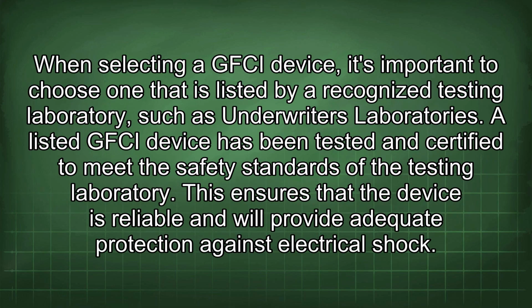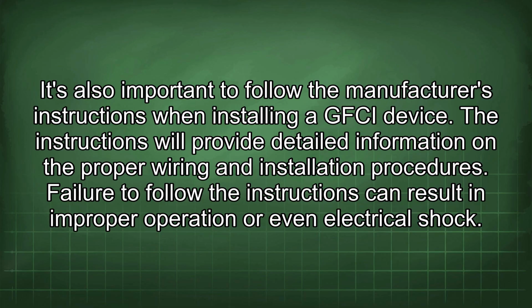When selecting a GFCI device, it's important to choose one that is listed by a recognized testing laboratory, such as Underwriters Laboratories. A listed GFCI device has been tested and certified to meet the safety standards of the testing laboratory. This ensures that the device is reliable and will provide adequate protection against electrical shock. It's also important to follow the manufacturer's instructions when installing a GFCI device. The instructions will provide detailed information on the proper wiring and installation procedures. Failure to follow the instructions can result in improper operation or even electrical shock.